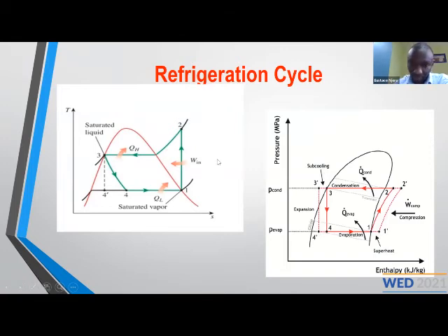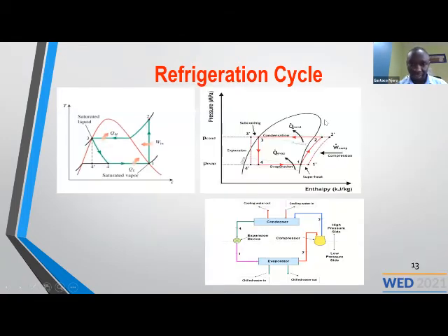You see in the refrigeration cycle, this is a TS diagram, this is the schematic figure. So on the evaporator side, where you do the cooling or you do the chilling of water, it's represented by this bottom line 4-1 in both the pH and the TS diagram. The compressor area is represented by 1-2, and this is the condenser area where you throw away heat which you have absorbed. And this is the throttling valve or the expansion valve, which is used to change.